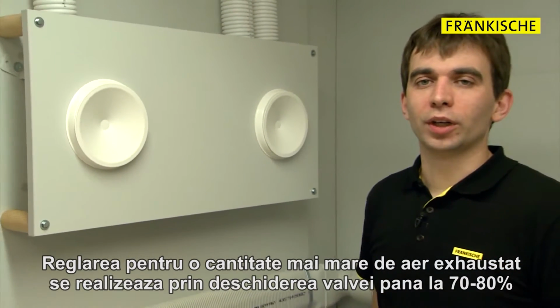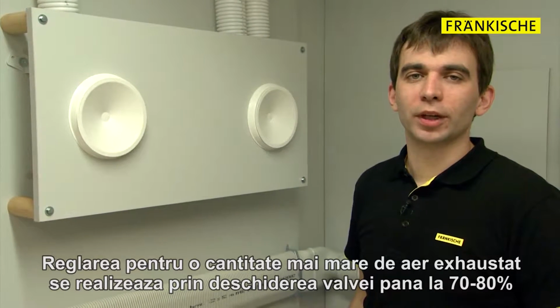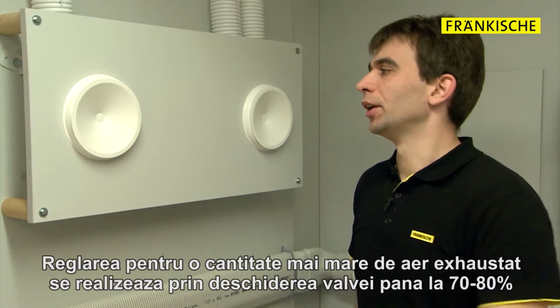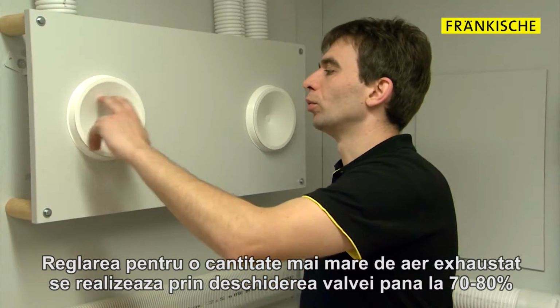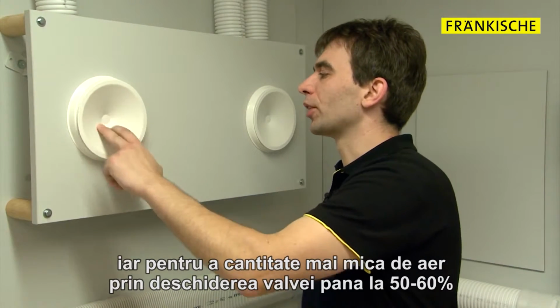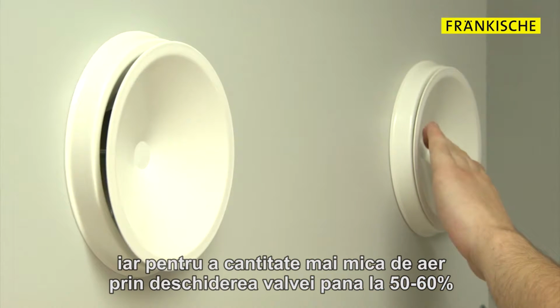There is a simple rule of thumb that can be applied towards presetting the supply and extract valves. The valves furthest from the manifold are opened by about 70 to 80%, and the ones situated closer by about 50 to 60%.